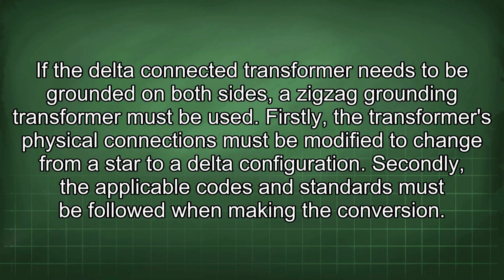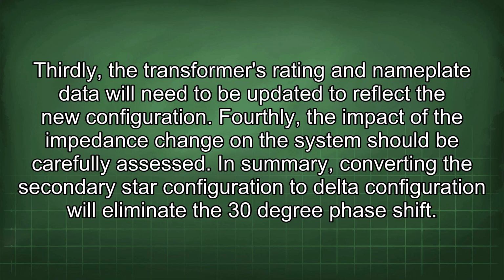Firstly, the transformer's physical connections must be modified to change from a star to a delta configuration. Secondly, the applicable codes and standards must be followed when making the conversion. Thirdly, the transformer's rating and nameplate data will need to be updated to reflect the new configuration. Fourthly, the impact of the impedance change on the system should be carefully assessed.